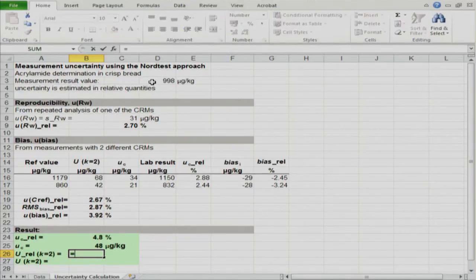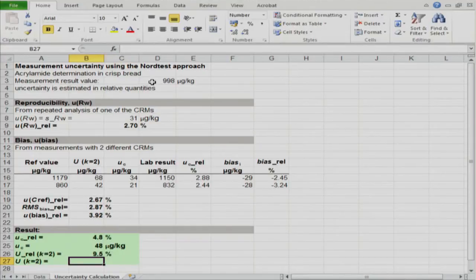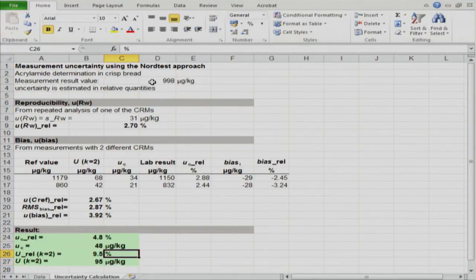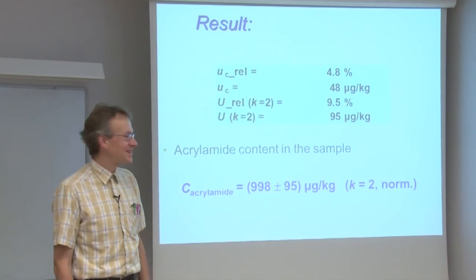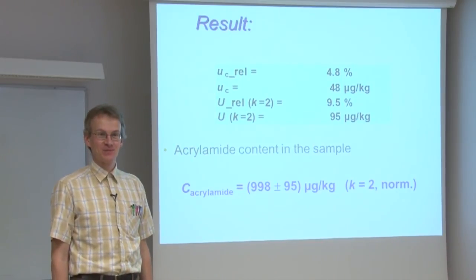The expanded uncertainty is found by multiplying the combined standard uncertainty by the coverage factor, which in our case is 2. The relative expanded uncertainty is 9.5%, and the absolute expanded uncertainty is calculated by multiplying the combined standard uncertainty by the coverage factor of 2, giving the result in micrograms per kilogram. We have now managed to find the uncertainty for our result.